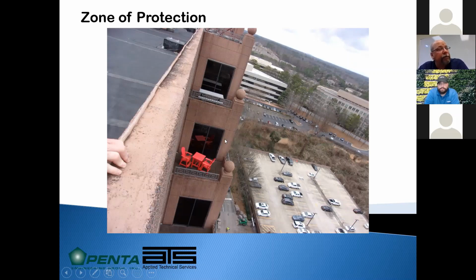It's a lot easier to do during building construction because all those details can be hidden in the columns. To add it at this point, air terminals on each level require 2 paths to ground. So we would either have to install additional down conductors on the interior, which means coring through every floor and routing that cable all the way to the ground, or installing it on the outside of the building in as inconspicuous a place as we can. Many building owners really don't want to see the exterior cabling.